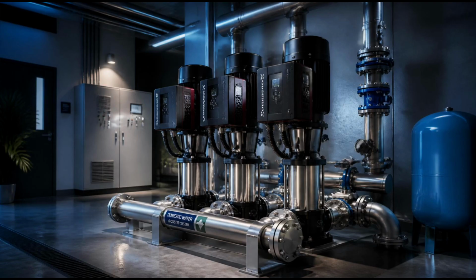The smoothness of that response is often managed by a variable frequency drive, or VFD, a device that controls the speed of the pump motor. Rather than switching the pump fully on or fully off, a VFD adjusts the motor's speed continuously, matching its output to exactly what the system needs at any given moment. A pump running at half speed uses significantly less energy than one running at full speed and then stopping. The result is not only more efficient operation, but quieter operation as well. No sudden surges, no sharp pressure spikes, just a steady, gentle adjustment to meet demand as it shifts throughout the day.